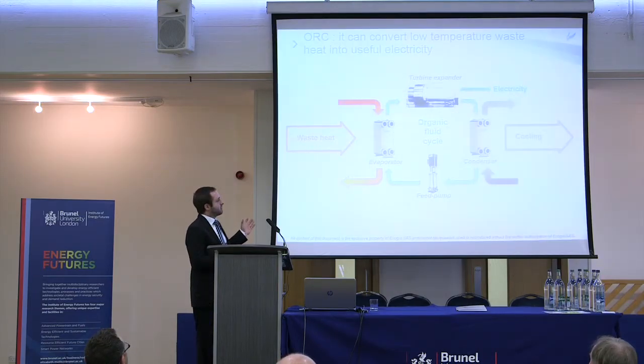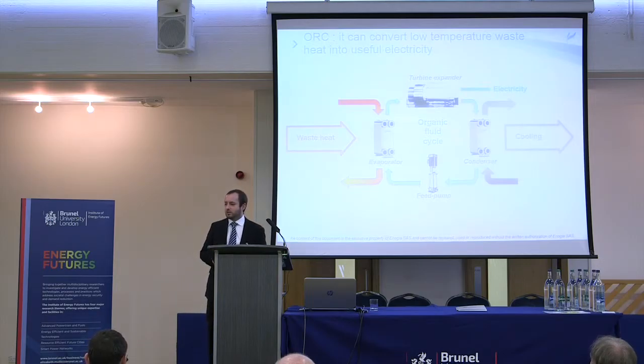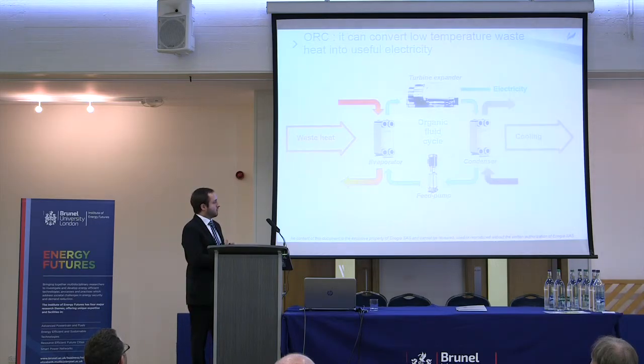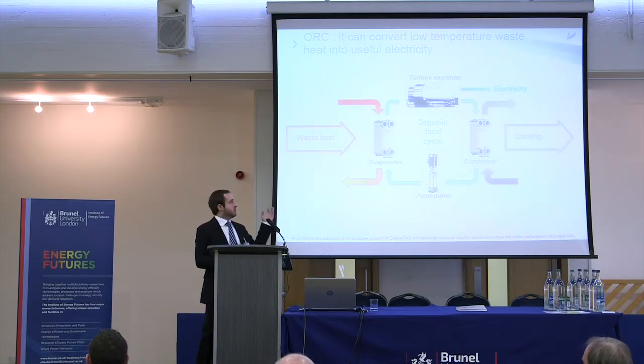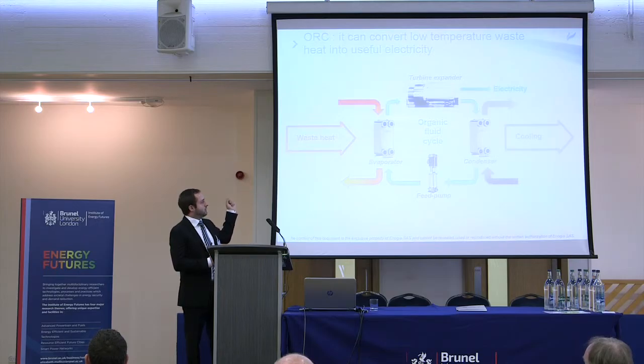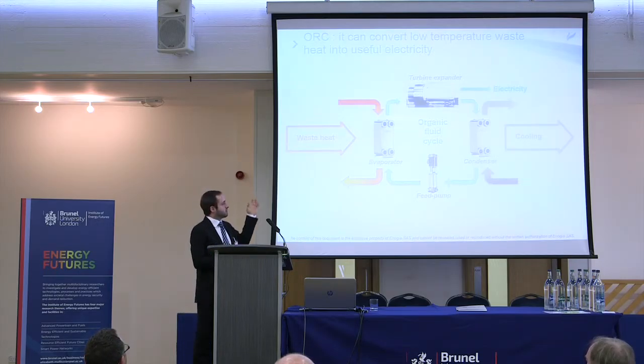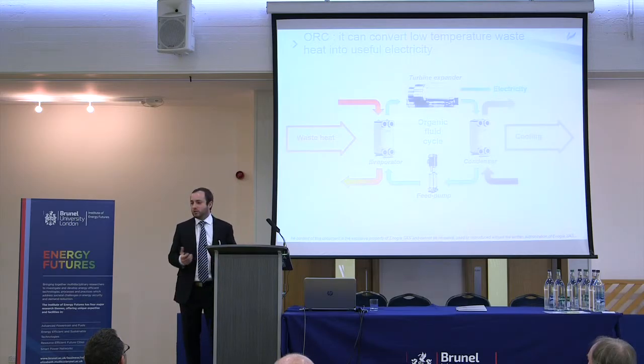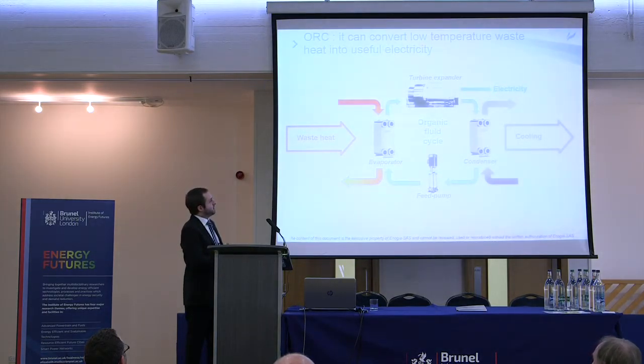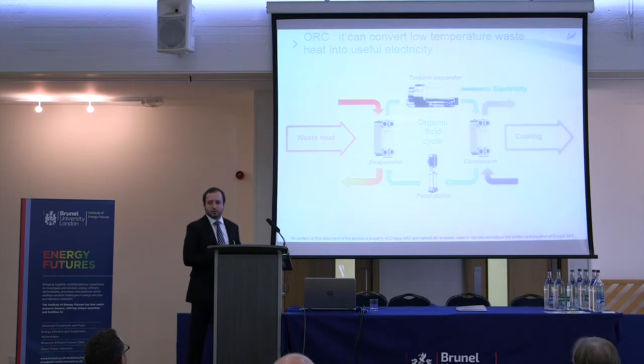An organic Rankine cycle, which I think many of you know, is a process very similar to the Rankine cycle used in most power plants worldwide. In an ORC, you take a refrigerant, pressurize it with a feed pump, then vaporize it in contact with the waste heat source in the evaporator exchanger. Here on this graph it's a plate heat exchanger, but it can be any technology, depending on the company or design team. Then you have a turbine expander, which expands the refrigerant, and you draw out the mechanical power to generate electricity.